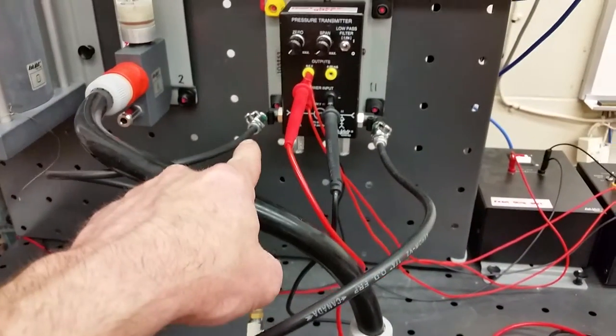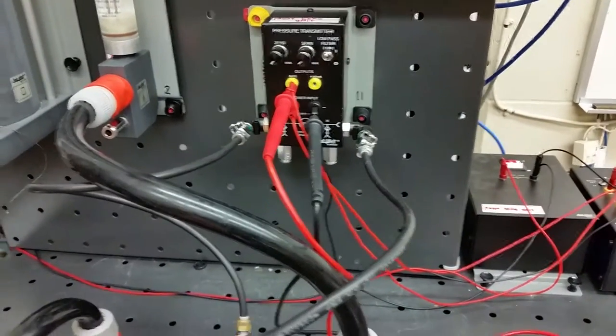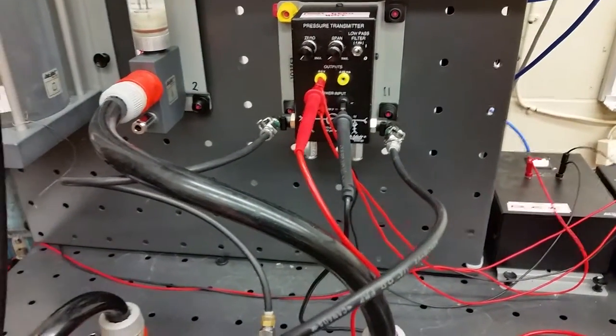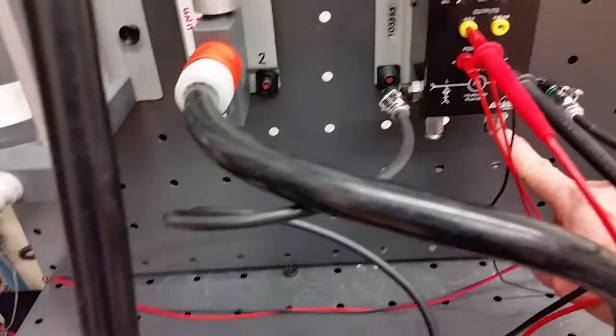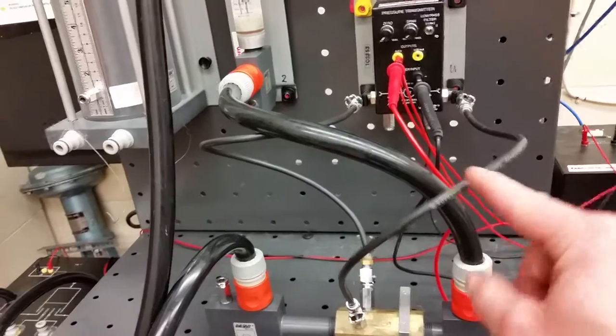As this was flowing, I took a longer tube and drained out from each of these stainless steel fittings — from here back to the pump and from here back to the pump. That gets rid of the air bubbles that develop in each of these pipes as soon as we connect them up.